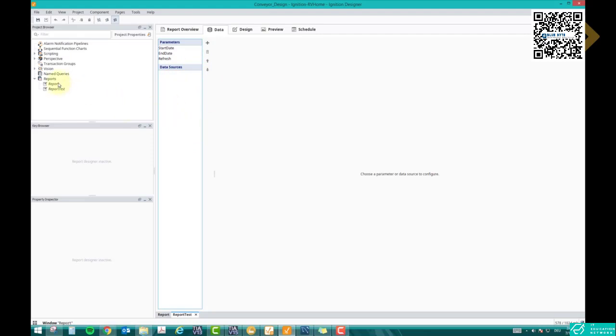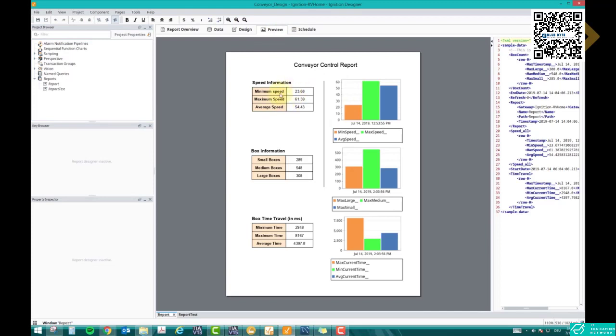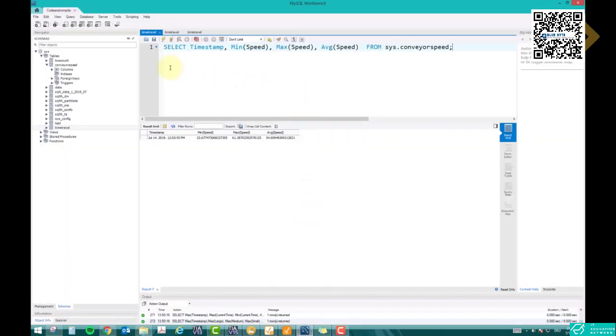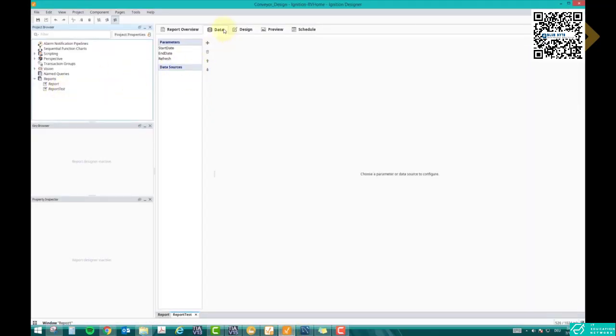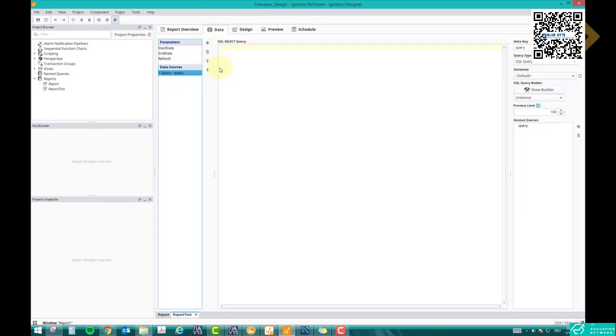Now comes the data source. We want information about speed minimum, maximum, average; box small, medium, large; and box travel time minimum, maximum, average. I have written three queries. The first query is: SELECT timestamp, Min(Speed), Max(Speed), Avg(Speed) FROM sys.conveyorspeed — this gives me the minimum, maximum, and average speed with the latest timestamp. Test your query in MySQL first, then copy the whole query and go back to Ignition.